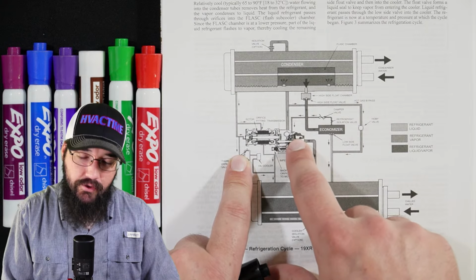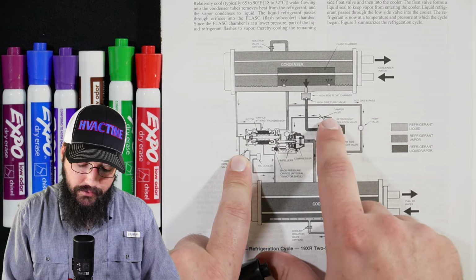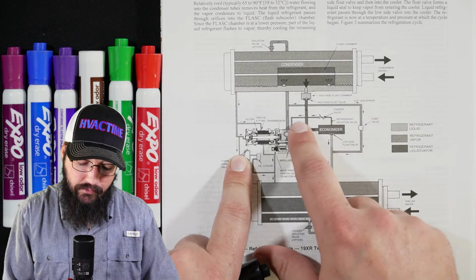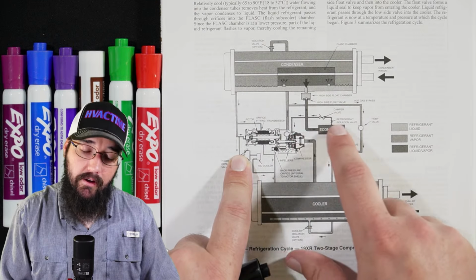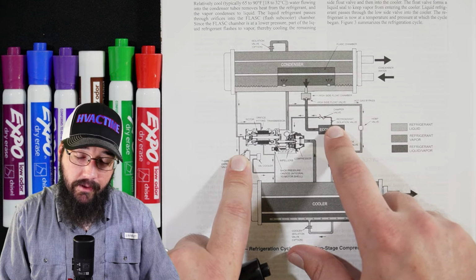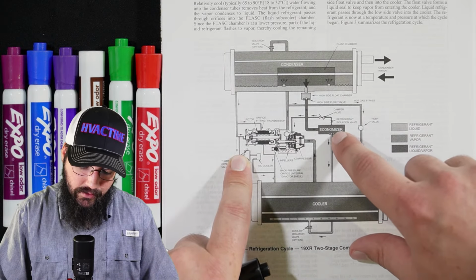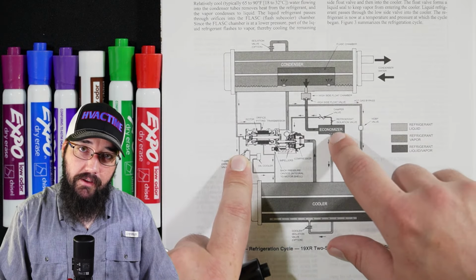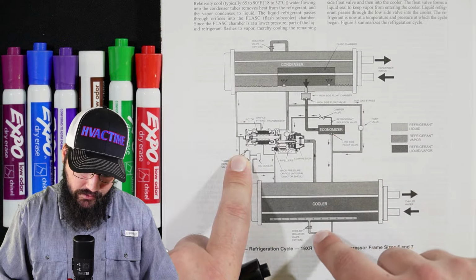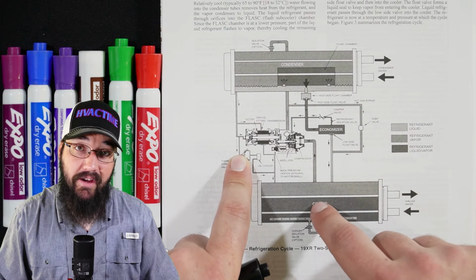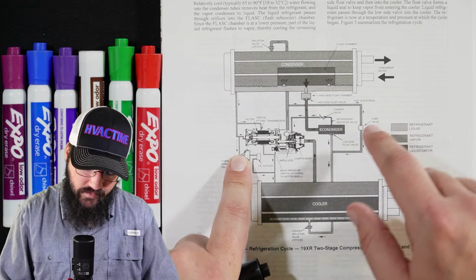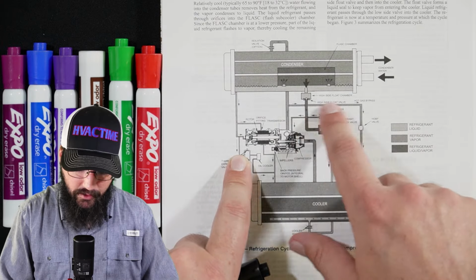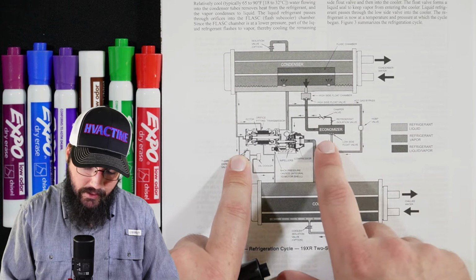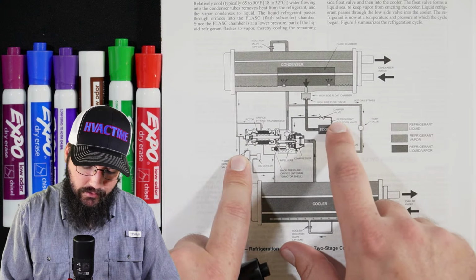The second stage impeller then draws off that vapor refrigerant that gets collected at the top of this economizer tank, and then there's another float valve at the bottom of this economizer that is metering flow into the evaporator itself. And then we can have other stuff in here, hot gas bypass circuits, yada yada yada. But that is the function of this.